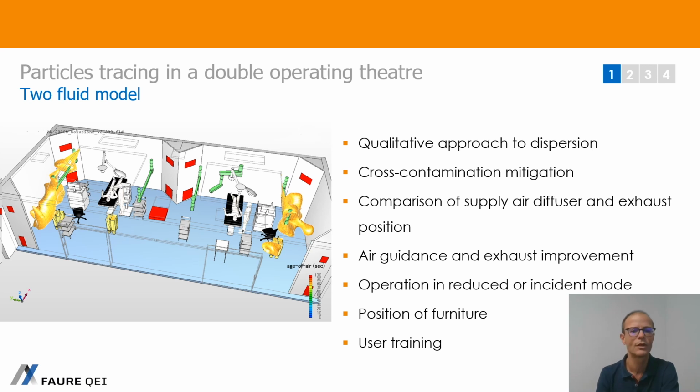We can move the exhaust a little bit. We had several scenarios for the exhaust, and we made a choice. We compared the performance of the different solutions we had. So that's a qualitative approach to the dispersion of particles you will see later. The objective is to mitigate the cross-contamination you can have between the two halves of the volume.